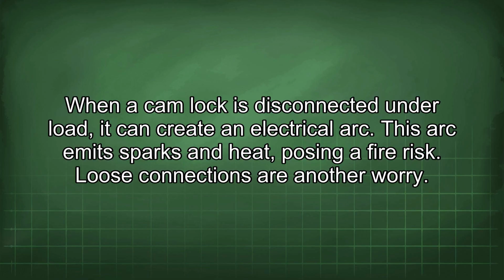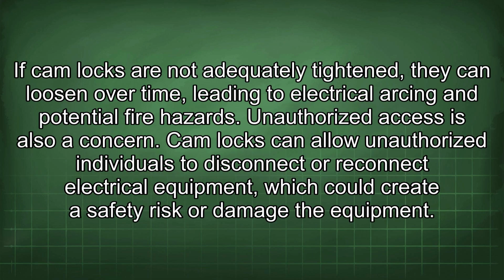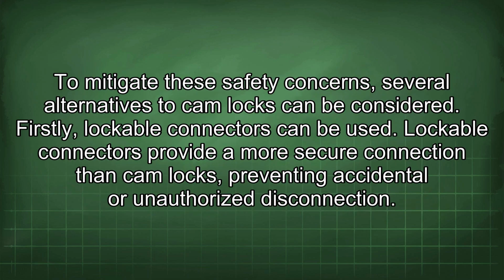Loose connections are another worry. If cam locks are not adequately tightened, they can loosen over time, leading to electrical arcing and potential fire hazards. Unauthorized access is also a concern. Cam locks can allow unauthorized individuals to disconnect or reconnect electrical equipment, which could create a safety risk or damage the equipment. To mitigate these safety concerns, several alternatives to cam locks can be considered.